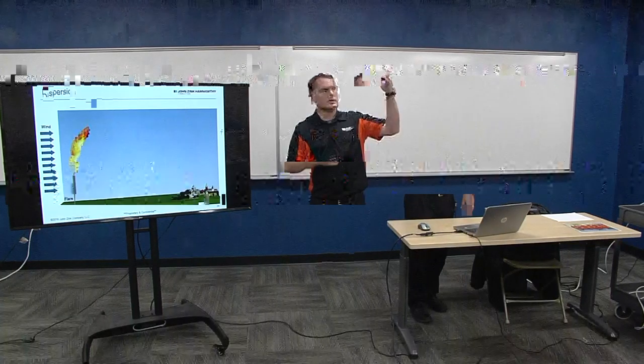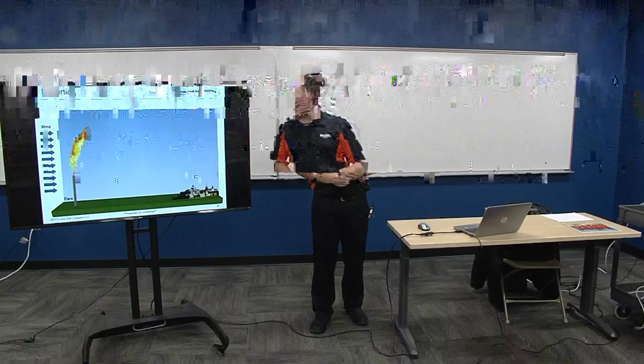So another thing affecting flares and their emissions is the dispersion. Flares are high for several reasons, right? You guys discussed radiation several classes ago, and then again on Tuesday. So flares are a certain elevation many times because of radiation, but a lot of times it's also because of dispersion. The gas that comes out of the top is not 100% combustion efficiency, so there is a little bit of hydrocarbon left over. The wind is going to tell it where to go. So dispersion is an important part of knowing what the ground level concentrations of all these byproducts are.